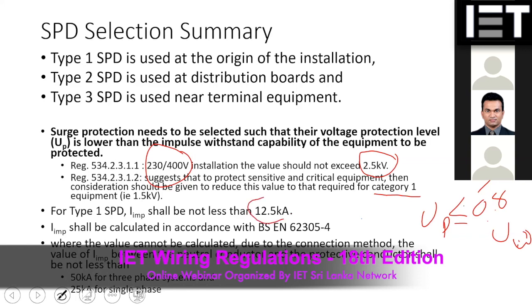And also there are certain requirements when you are going with the class 1 SPD. The I impulse value should not be less than 12.5 kilo amperes. When you have single phase and 3-phase, if you use 12.5 coming in, that should go through them, you will get 4 times 12.5, so that is 50 minimum. If you get the single phase, you will get 2 times 12.5, so that is 25. Those are the minimum requirements. So there are regulations for those things in the new standard.